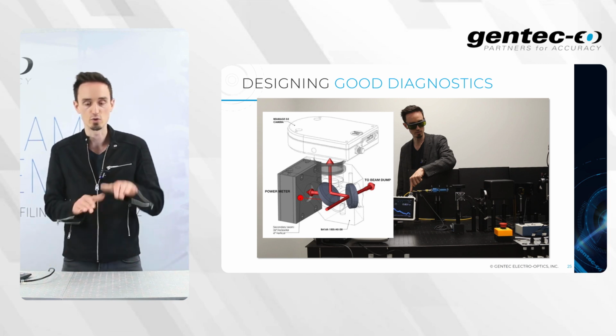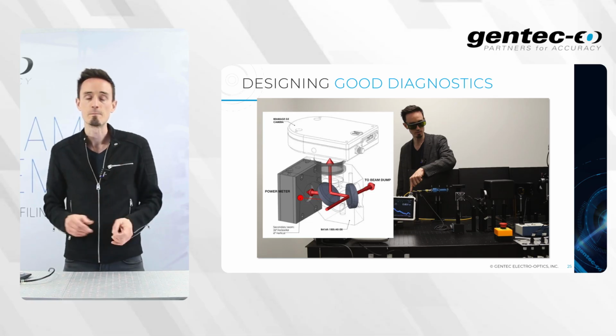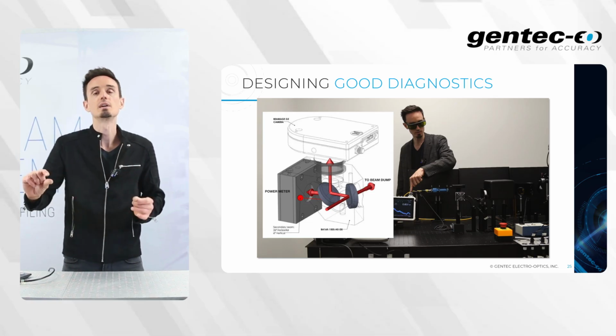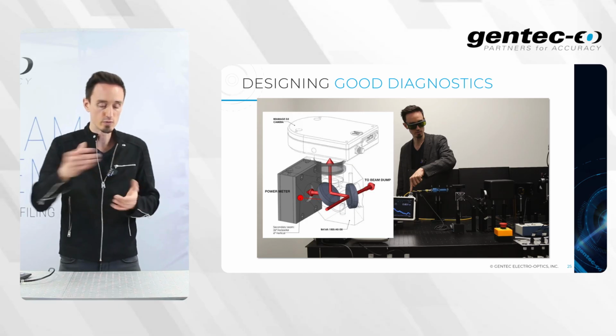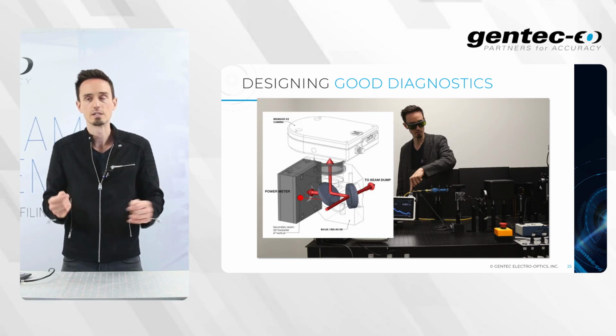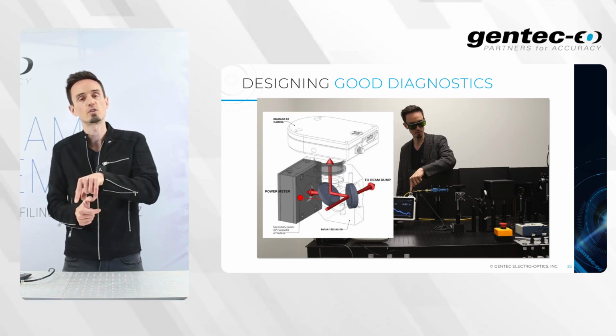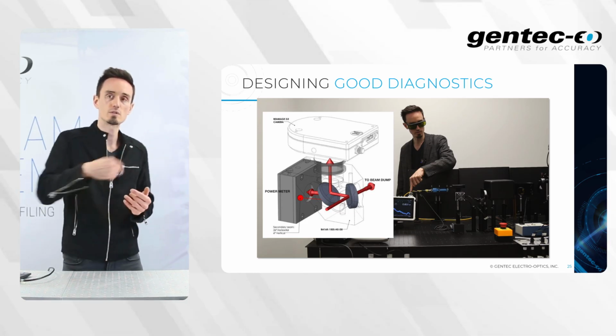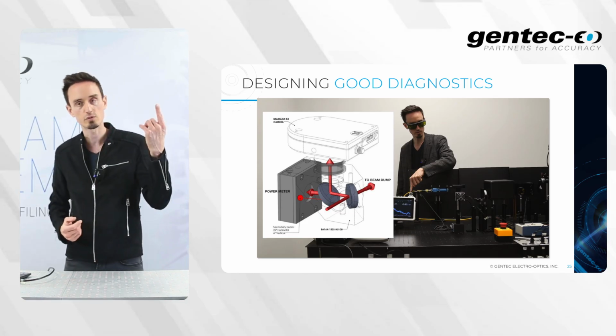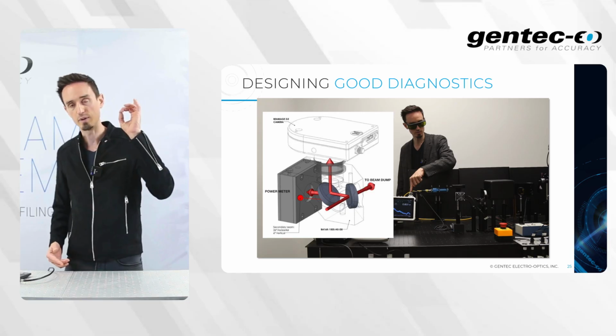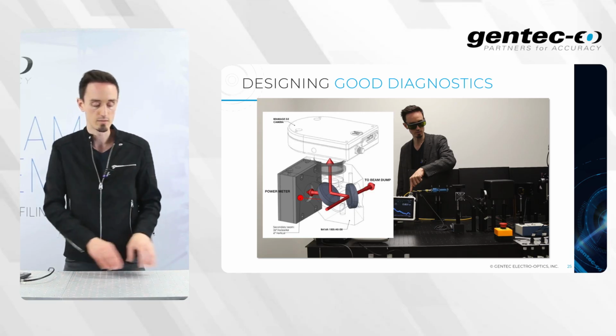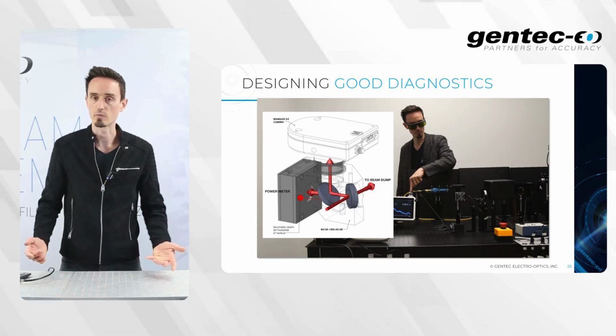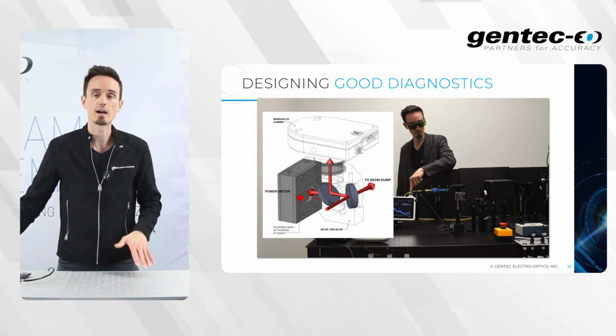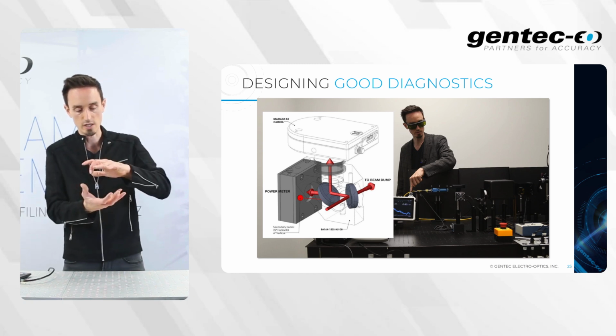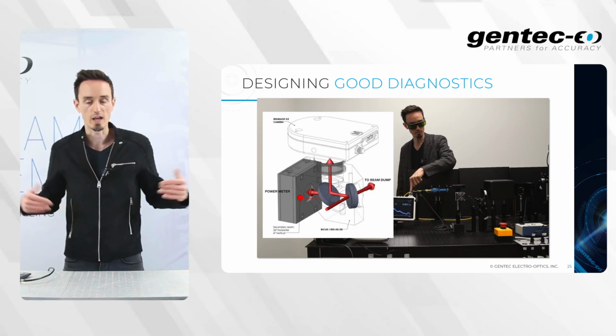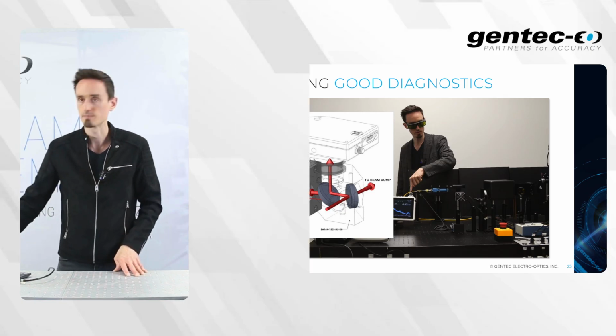That's an example of dual wedge beam splitter system with typically 92% of the incoming beam power that's transmitted through the first wedge at 1070 nanometers, then reflected off the surface of the first wedge goes to the second one, in transmission goes to a power meter, in reflection off the surface of the second one goes to a beam profiler. So you have a tool for inline power or energy and beam profile measurement. So that's great to attenuate down to safe level. Those systems in this package here go up to 500 watts. If you add water lines, it could go higher to kilowatt range.